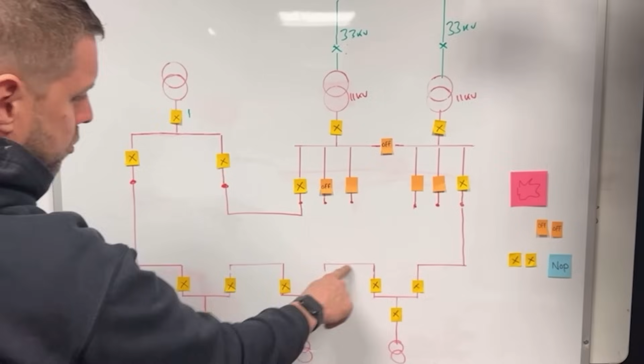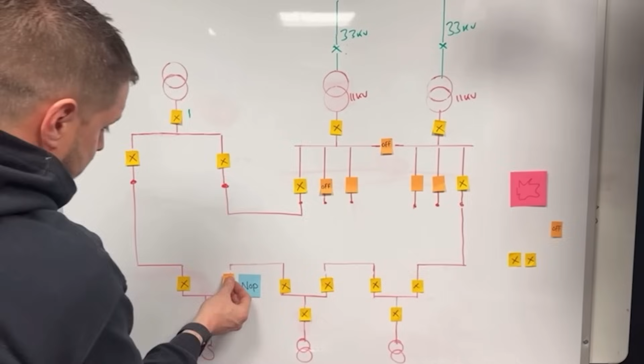But now you'll see we've created another bus section through the ring main. So what we do is have a normally open point. We take a point about halfway, which I'll make here, and apply a normally open point, and make that switch off. Now that does something a little bit weird, and what it does... can you work it out? It's made 2 radials.